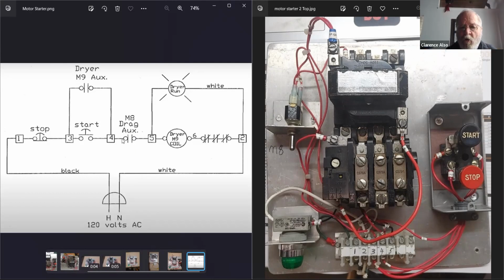Maybe, because there are 2 components between here and the known good point. This is known bad at 0, and you were expecting 120 — this was 120. There's a wire and there's an auxiliary contact. Could it be the wire? It could be the wire. So then probably you should go to the far side of the auxiliary and check the wire.